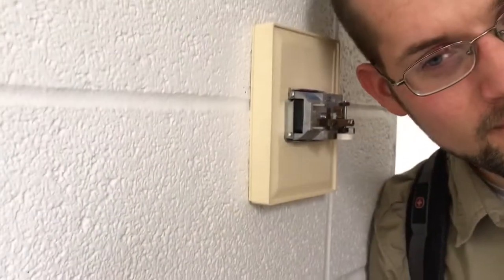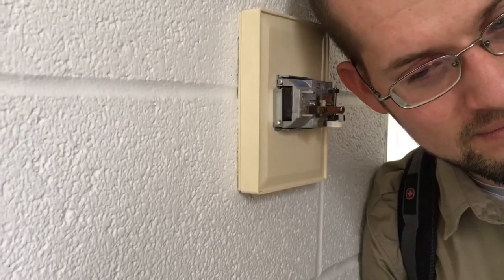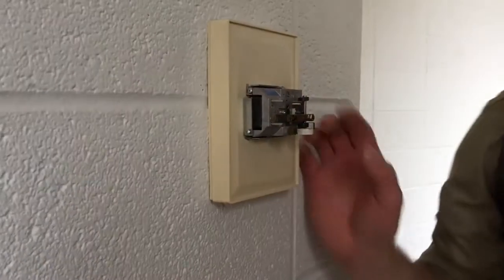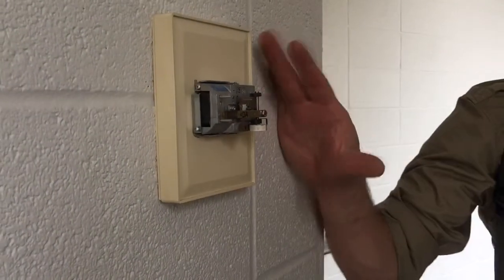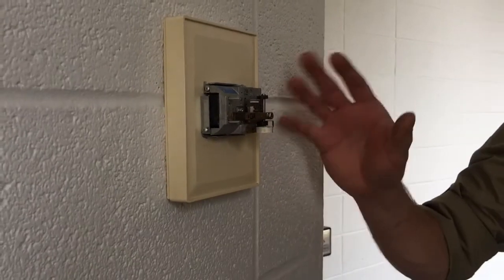The next thing I like to check is if you can hear an audible leak through the thermostat. So I turn it all the way to full cooling and just listen to it. And this one's got a minor leak. You can't hear it unless you're right next to the thermostat. So more than likely, it's got just a minor leak that could be fixed to save on compressed air, but it's going to control set point adequately enough.